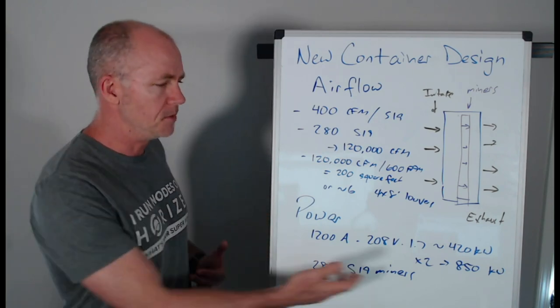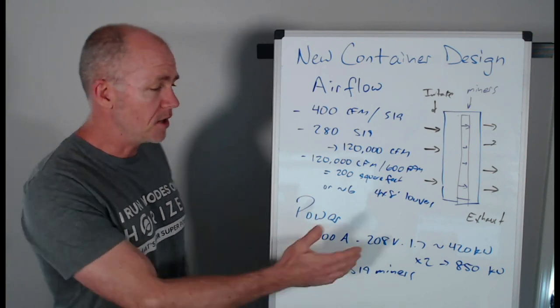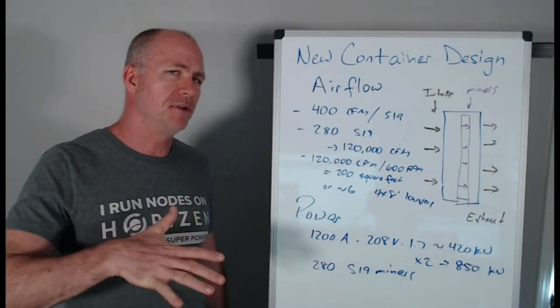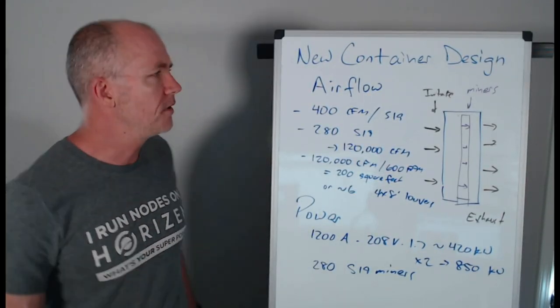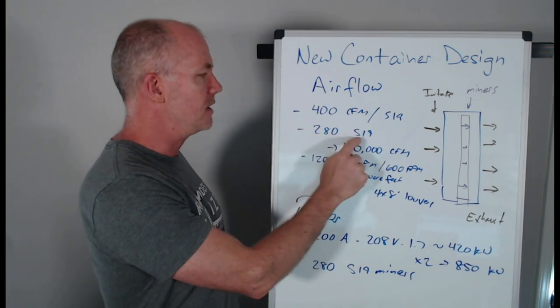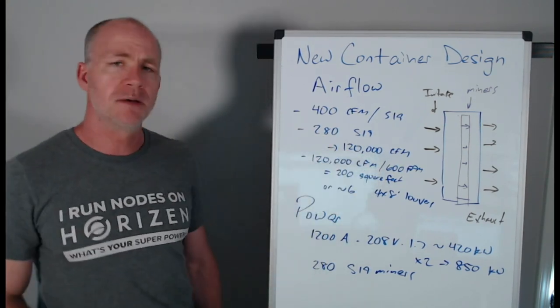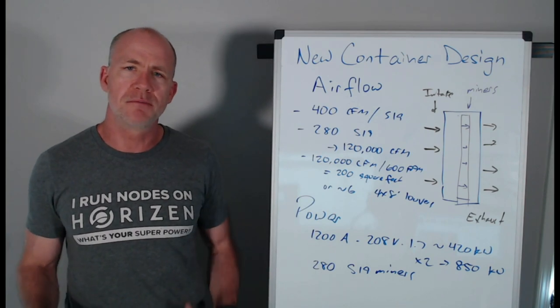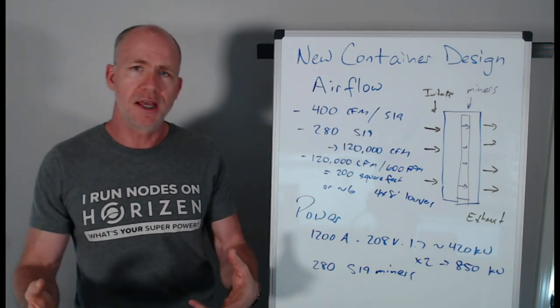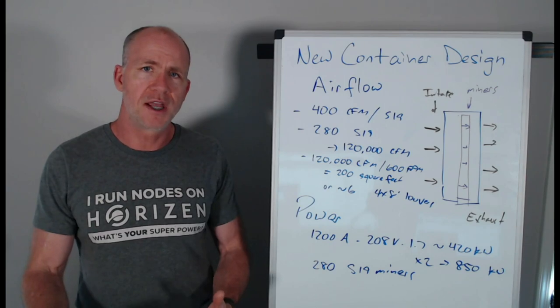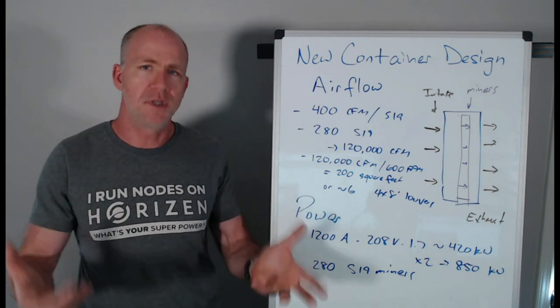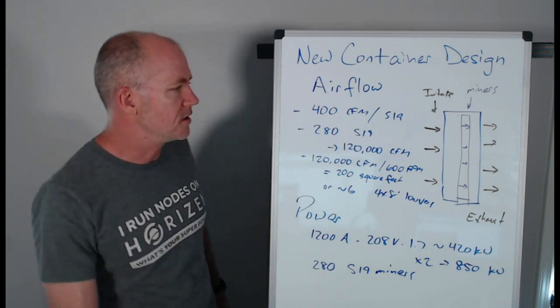So these are really rough numbers. So 1200 amps, 208 volts times 1.7 when we go from three-phase to single-phase because three-phase is a lot more efficient and we break it out. That gives us about 420 kilowatts max for each large 1200 amp panel. Now we got two of these and so we could theoretically do 850 kilowatts into this container. If it was 240 volts, you'd be up above a megawatt for a container design. But if we're talking about 850 kilowatts that we can supply, how many S19 miners really roughly is that? 280. Knowing that we have about 400 cubic feet per minute per S19 and 280 S19 miners, that really roughly comes out to 120,000 cubic feet per minute of airflow that we need to bring in.